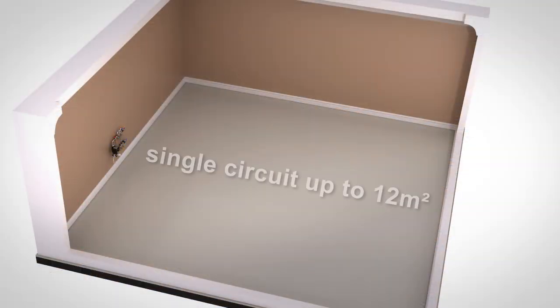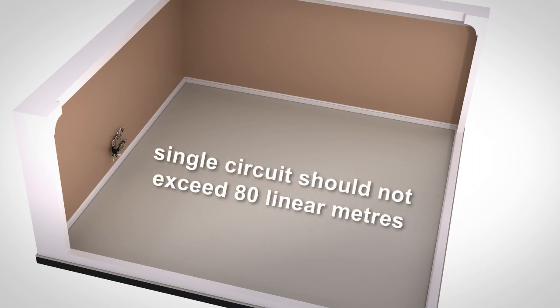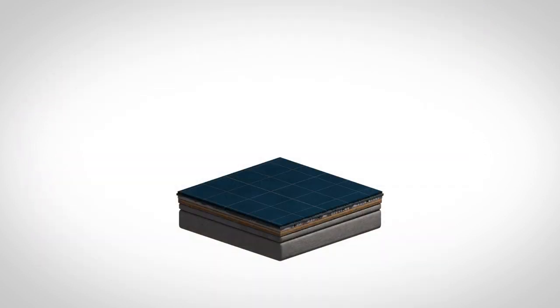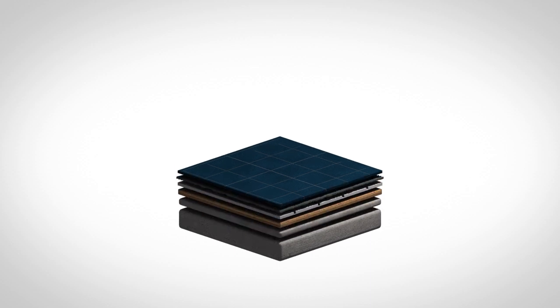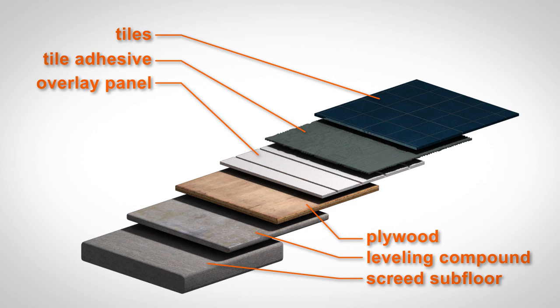A single loop circuit can cover up to 12 square metres. A room larger than this will require a manifold to allow for multiple circuits. A single circuit should not exceed 80 linear metres of pipe. Our overlay floor panels are recommended for most ceramic or stone-tiled floor coverings and they must be installed on a suitable structurally sound and level subfloor, such as plywood or solid screed.